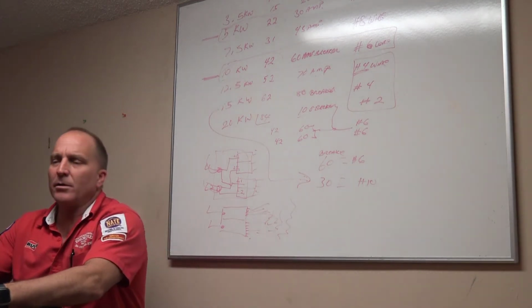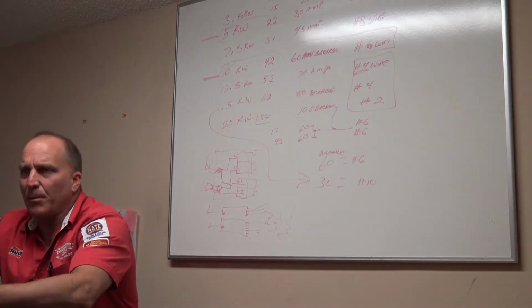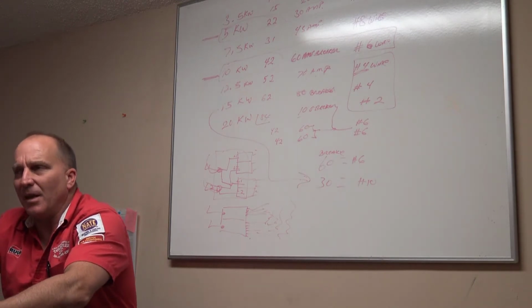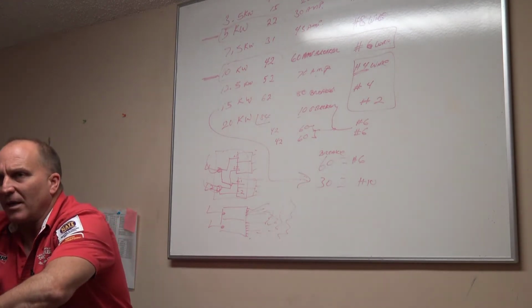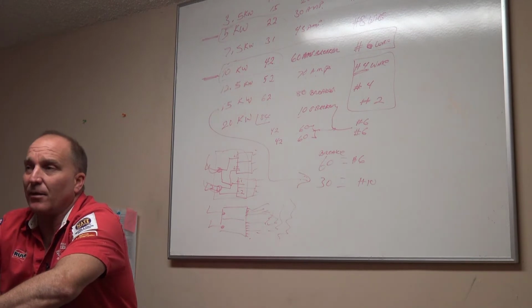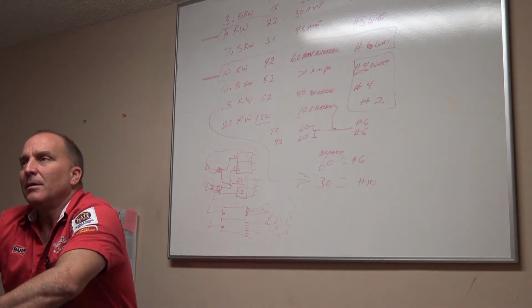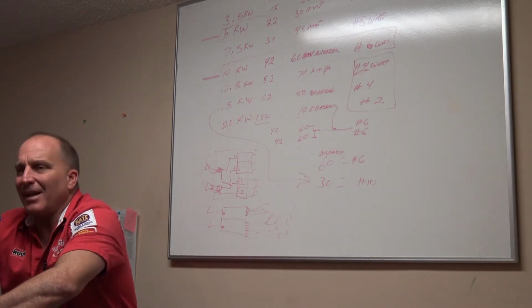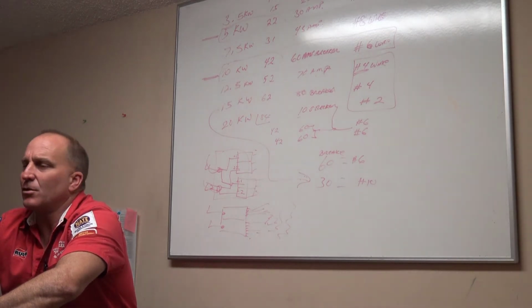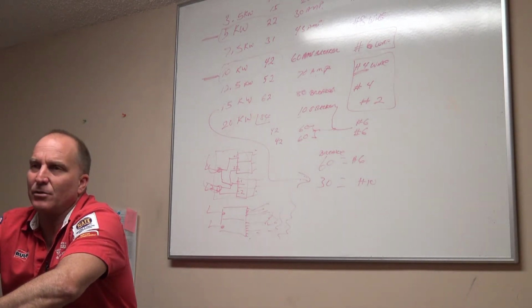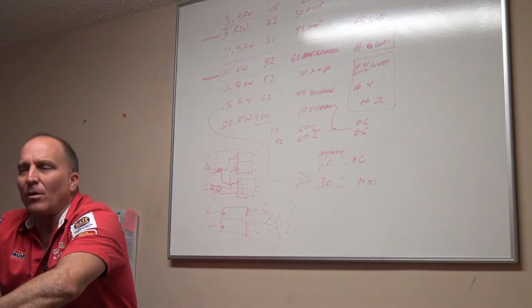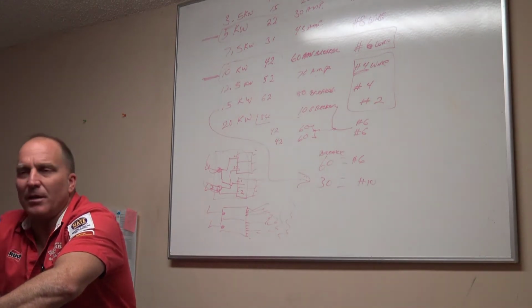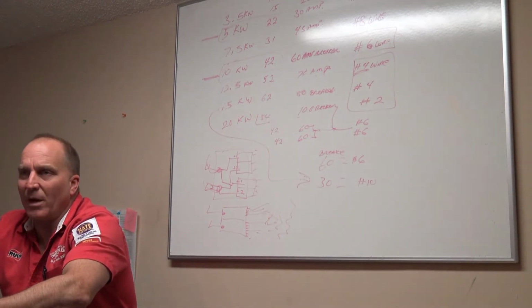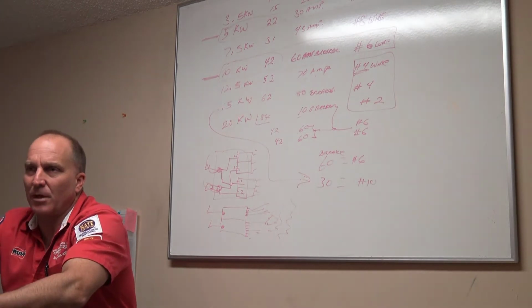Because if you hook W1 and W2 separately, and you got a 15 kW heat system, then it'll turn on 10 kW and turn on 5 for your secondary heat. If you have a W1, W2, and you have a 10 kW heat system, you just use W1, W2 together, because 2-stage heating on 10 kW system doesn't do you any good, okay? If it's 20 kW, you can draw 10 and 10 on W1, W2.